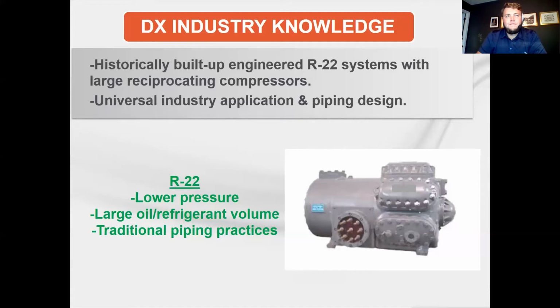And like Randy said, you knew that the suction line needed 1,000 feet per minute face velocity up the pipe to get the oil back to the compressor. All the manufacturers followed the same rules back then. These compressors had unloading capabilities so that the volume of refrigerant that they pumped would change with the load. And so some of the pipes required double suction risers to make sure the oil could travel uphill to the compressor again. Do you want to advance the slide, Randy?